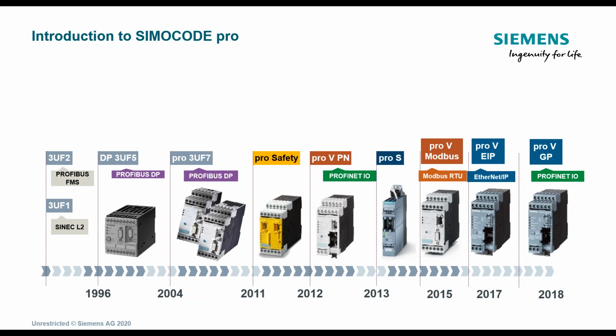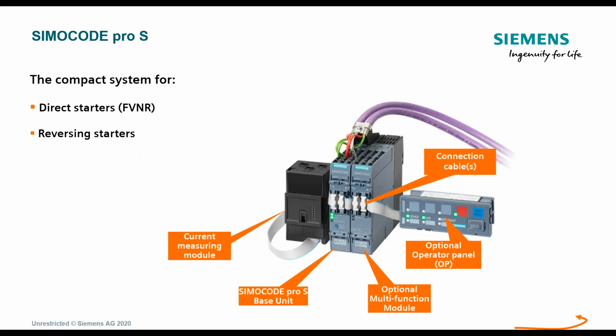This one can come with a single port or a dual port switch, but it is a little more cost effective for some more simplistic systems, where you don't need the full arm of a ProV high feature version. This one will only allow you to expand with either one digital or one analog card. It's not as expandable as the standard high feature Profinet, and we'll get into that just a little bit further. Okay, so the ProS is only for direct starters and reversing starters. It's very compact. It only speaks Profibus.